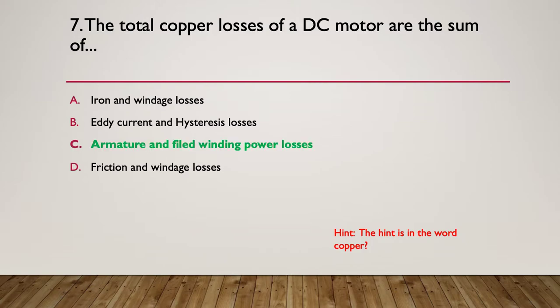So the answer at this time is armature and field windings. Iron, no copper involved. Windage, no copper involved. Eddy currents are around steel. Hysteresis losses are around steel. Friction is around the bearings. Windage is around the rotor rotating through the air. So just by process of elimination, A, B and D have nothing to do with copper. Armature is made of copper wire and the field winding is made of copper wire. So obviously those are the copper losses.